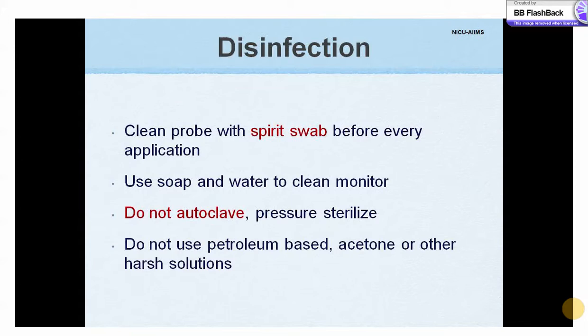Disinfection is as important as careful handling. The probes should be cleaned with a spirit swab before every new application. The front panel can be cleaned with soap and water. The unit does not need autoclaving or pressure sterilization. Never use petroleum-based products, acetone, or other abrasive liquids to clean.